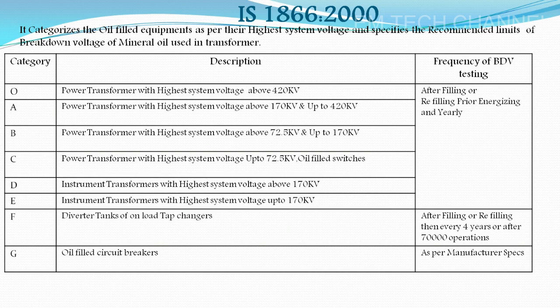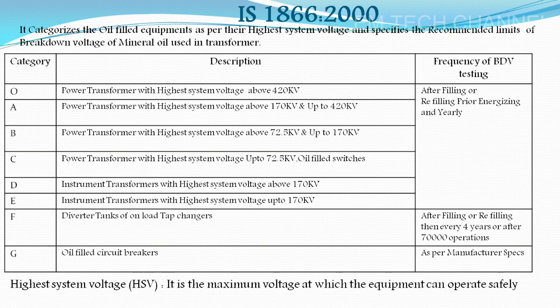The frequency of breakdown testing is as follows: from category O to category E, the test is conducted after filling or after top up, before energizing, and it should be conducted once yearly. For category F, that is for diverter tanks on on-load tap changers, it should be conducted after filling or after top up, then every 4 years or 70,000 operations. And for category G, oil filled circuit breakers, the frequency is as per the manufacturer's specifications. And what is the highest system voltage?